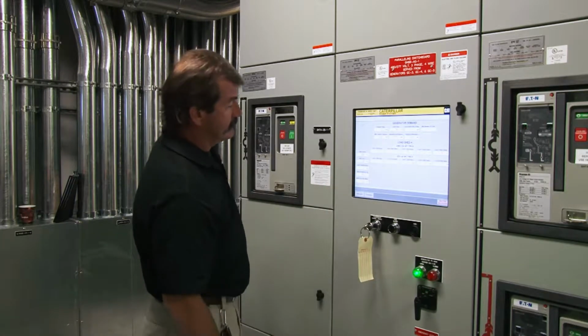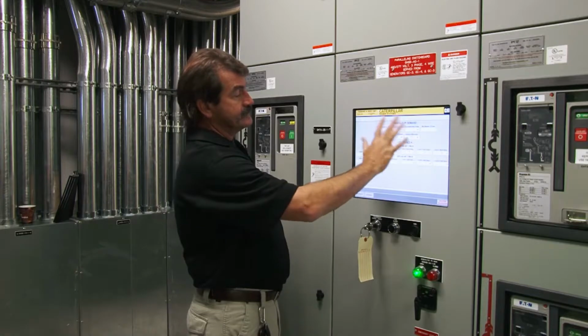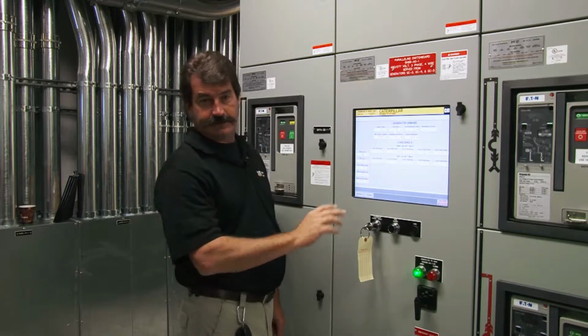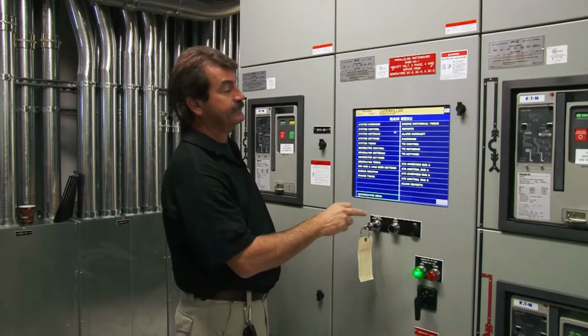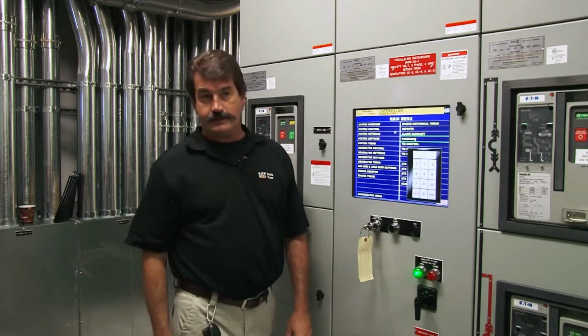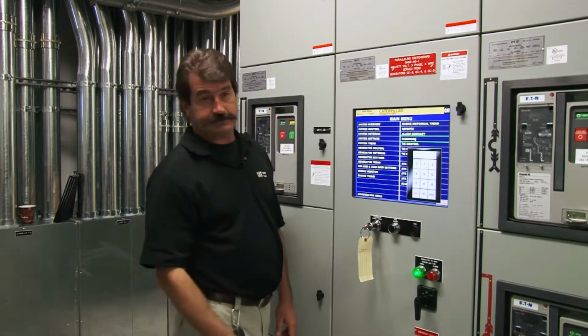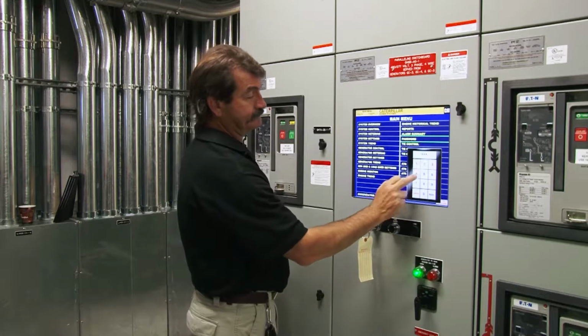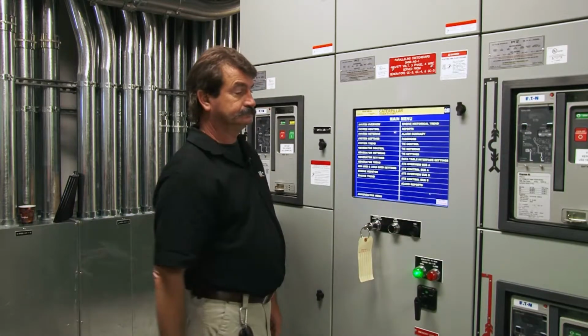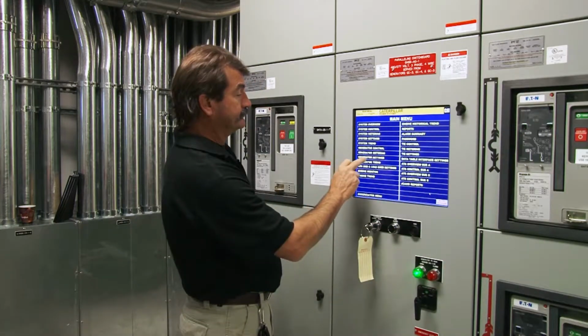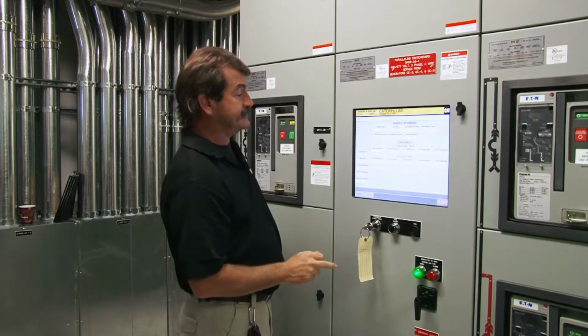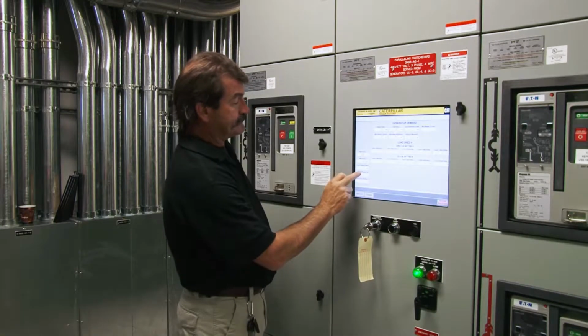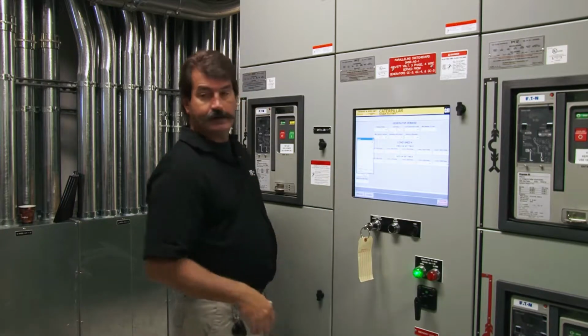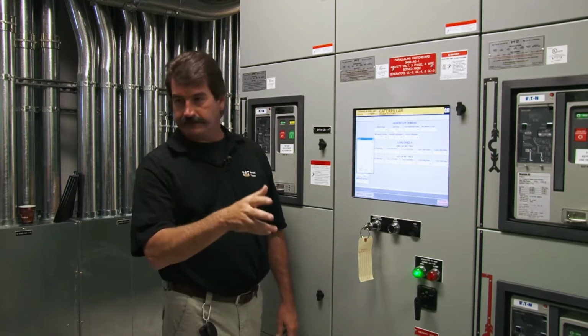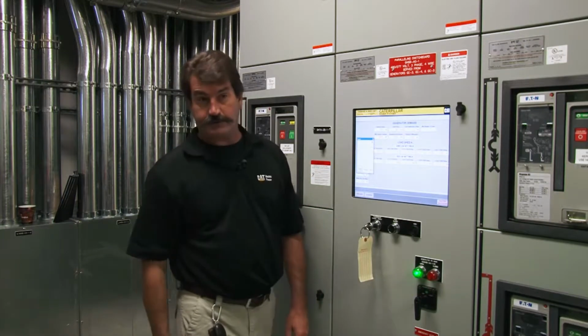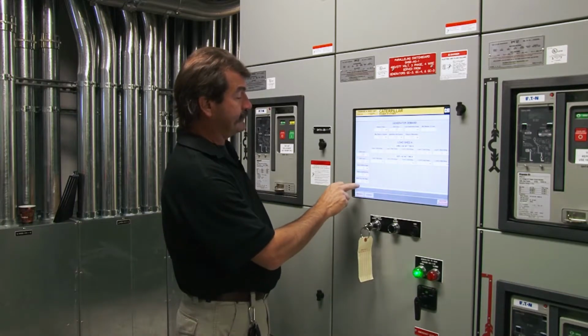Okay. These settings that you see up here, any settings that you have to come up with, you just enter your password and do your settings. Now you can go to gen demand and load shed settings. You can go here to under frequency trip and double click it and have it come up, and you can set what you need to. So it's 55 hertz at 3 seconds.